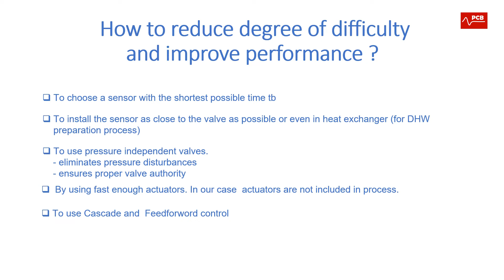Cascade control is one solution. We get it by introducing an additional measuring point, in our case T1, in such a way that we split the process in two parts. And then we also introduce an additional controller, which is usually P-type, and we get two loops, the inner loop, or nested loop as it is sometimes called, and the outer loop. And this is the way to improve performance of a process with a high degree of difficulty.